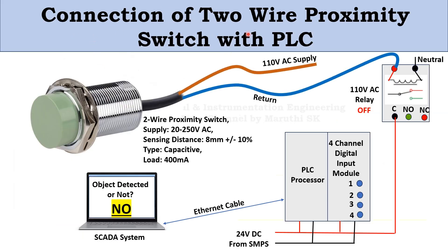Let's understand the connection of a 2-wire Proximity Switch with the PLC. This is the 2-wire Proximity Switch, consisting of a brown wire and a blue wire. The supply can be 20 to 250V AC — in this field we have applied 110V AC. The sensing distance is 8mm plus or minus 10%. The type is Capacitive, and the maximum load that can be connected is 400mA.